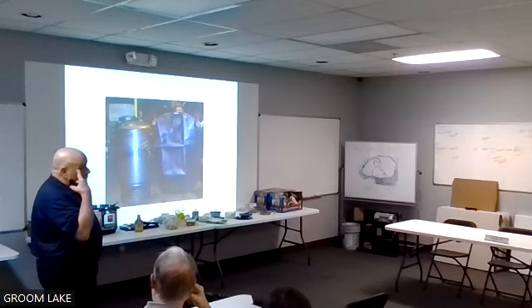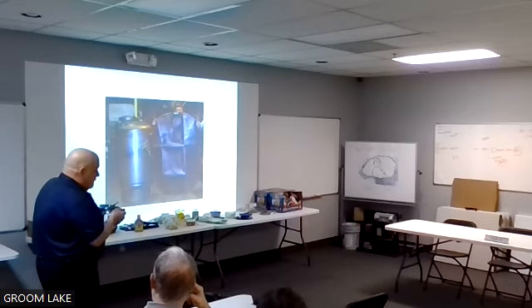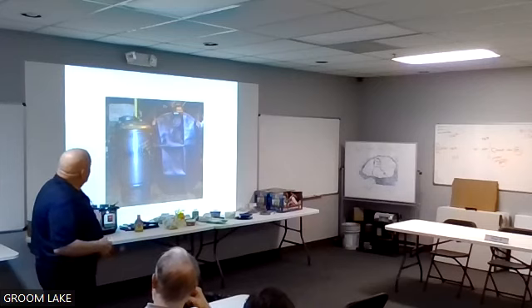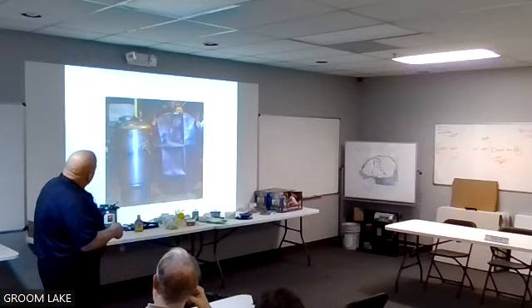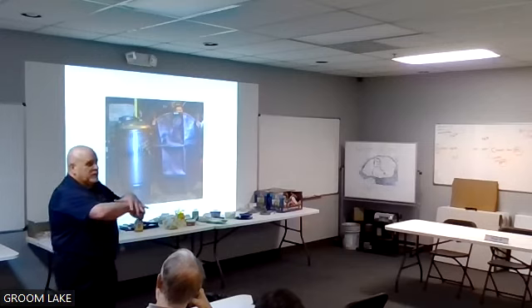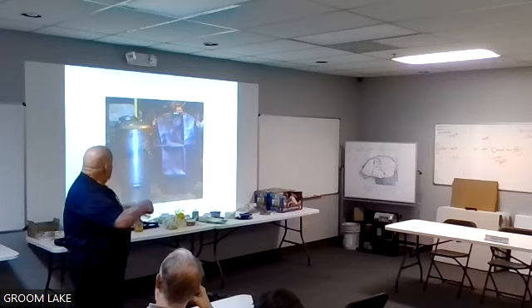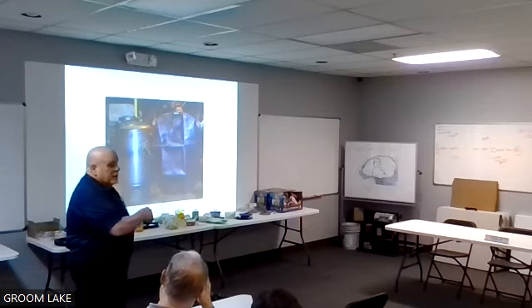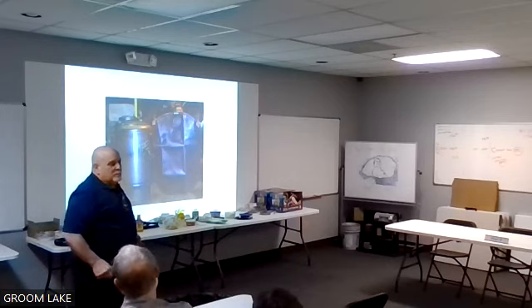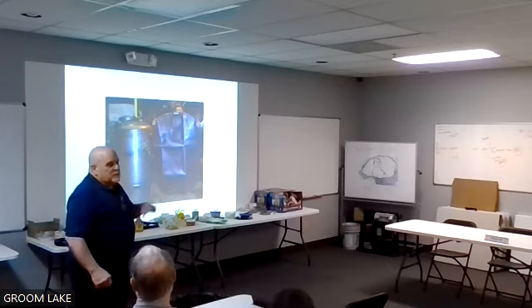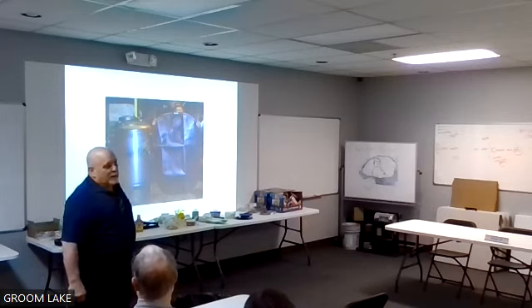These are all made of heavy butyl rubber. These are kind of a pain to do, but you can collapse this and pull it out through here. The best way I found to do them is take all the air pressure off, get the water out of them. Open this, and this neck actually is your gasket. This flange sits upright and sits on here, and that top cover actually sandwiches it as your gasket. So once you take that top cover off, you can get a choker around this, lay it on its side, put it on a chain pull, chain the tank down and just pull it out.